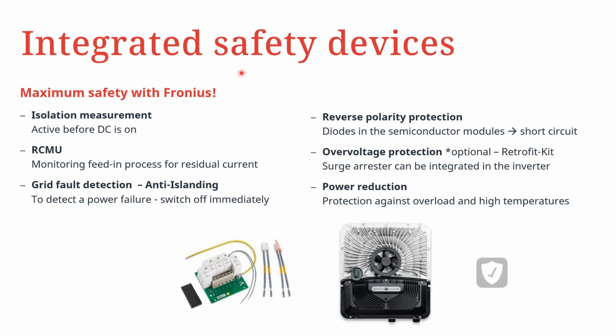As far as the safety devices that are integrated, we have the isolation measurement that is done before DC power is put on, before generation in the morning. We have the RCMU for monitoring the residual currents during the feeding process. And then you have the grid fault detection, or the anti-islanding, that allows the inverter to switch off immediately if there is a grid disconnection. So when you have a grid disconnection and you have a battery connection, it is important to also wire the GEN24 up for full backup functionality, so that when the anti-islanding is activated, then the inverter with the full backup wiring can be enabled to use battery storage to continue powering your loads.